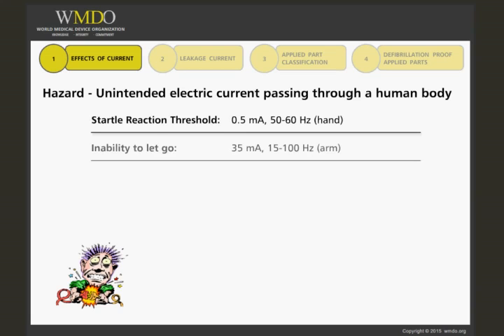The inability to let go occurs at 35 milliamps, 15 to 100 hertz, through the arm.